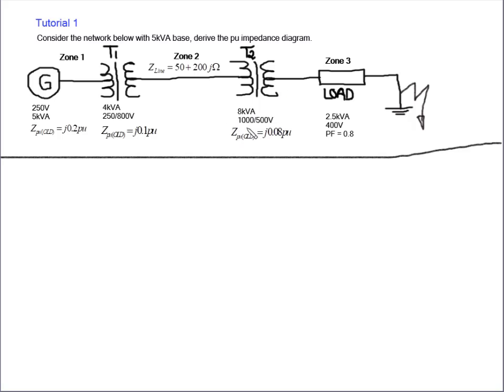...which has a ratio of 1000 to 500 volt. But make no mistake here that your secondary voltage here will be 500 volt, no. Because this transformer primary voltage of 1000 is not the same as this transformer here, secondary voltage of 800 volt. So you have to do a transformer calculation of the secondary voltage based on that. So there is a formula to do that. So that's basically how you focus per zones in order to limit your mistakes.